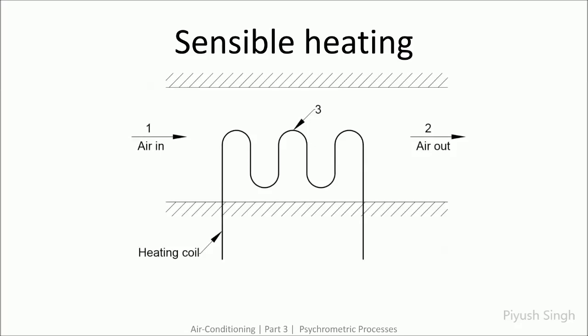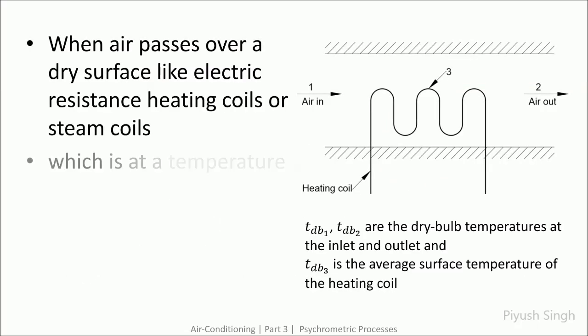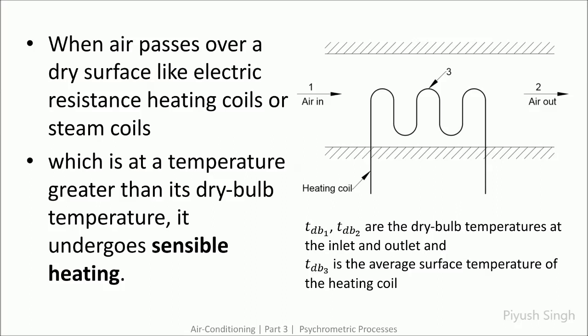The second process is sensible heating. If we have a heating coil — either an electrical heating element or a steam coil — at a temperature higher than the dry bulb temperature of incoming air, there will be net heat transfer from the coil to the incoming air and the outlet air will be at a higher dry bulb temperature. Since there is no moisture addition or dehumidification, the total moisture content remains the same at the outlet.